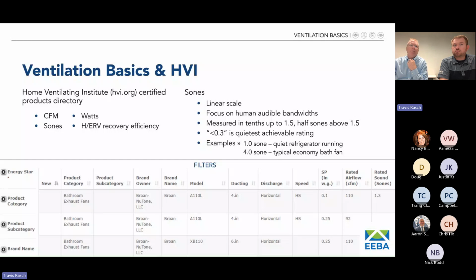So I'm going to switch gears a little bit and talk about some ventilation basics. For any of you that are relatively new to ventilation, one very important organization is HVI, the Home Ventilating Institute. Great if you get a few minutes to go to their website, hvi.org. HVI is both the certification body. So when you see that a bath fan or range hood or ERV is HVI certified, you can trust that the CFM level, the sound level, the wattage, the SRE, you can trust those numbers. And it's also a trade organization. So on their website, they have something called their certified products directory. The bottom half of the slide, you kind of see a sample there. You can sort by manufacturer, by type of ventilation product, and you can see any certified model, what's its airflow at different static pressures, what's its sound level, wattage, again, SRE in the case of HRVs and ERVs.